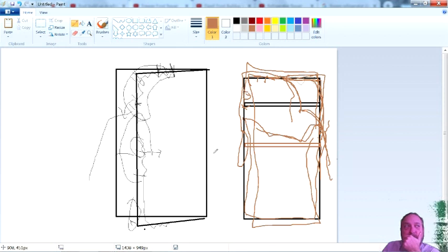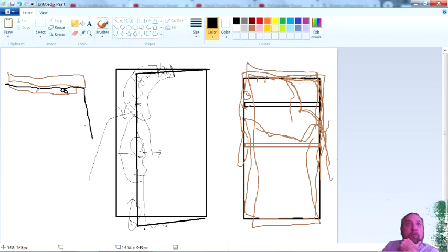Does the gasket come with an adhesive, or is it an adhesive that we have to apply ourselves? There is no adhesive. The older gasket was this thick, but it had a flap in the back. And the door liner, and I'll use a different color, the door liner overlapped the gasket. And on the real old ones, the screws went through the plastic liner, through the gasket, and then the door was behind it back here. Okay? So the gasket had to be tucked in behind this.